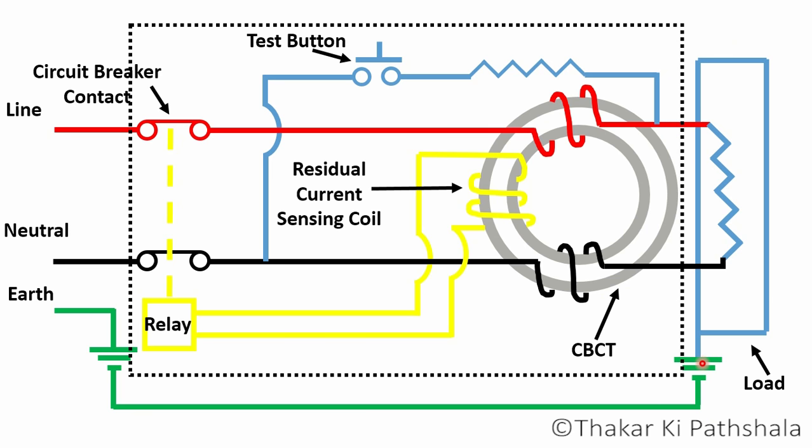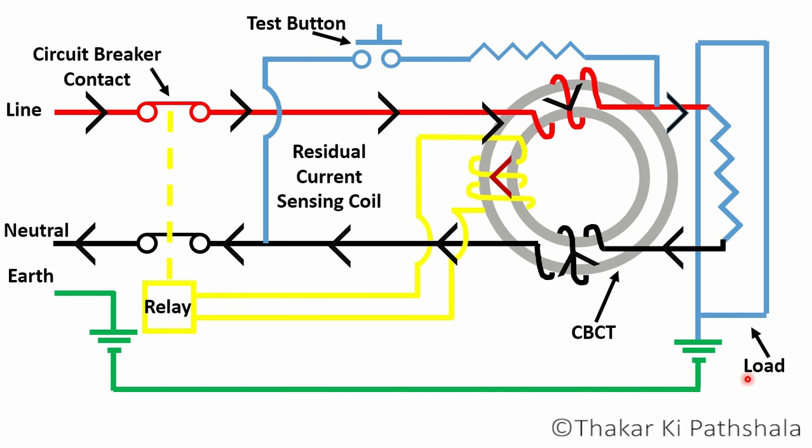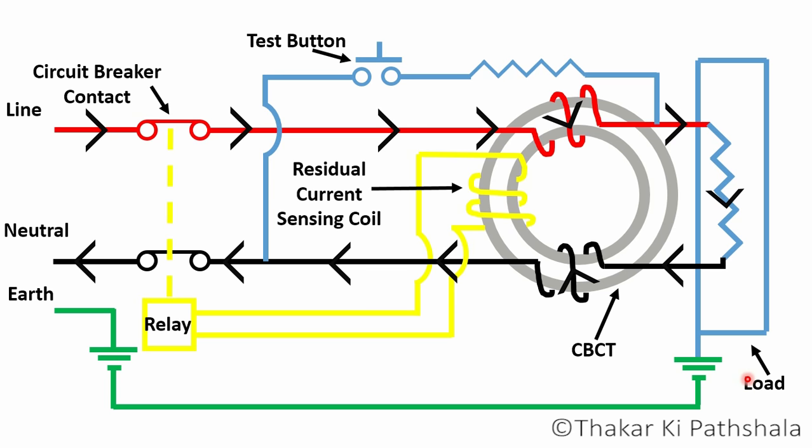Let's take the first scenario in which everything works fine. There is no fault. In this case, the current entering from the line conductor will be equal to the current leaving from the neutral conductor, but the direction of both will be opposite. So as per Fleming's law, the flux will induce in the core. But as the magnitude is the same and the direction is opposite, they will eliminate the effect of each other. So there will be no residual flux in the core of CBCT transformer. So no flux will link to the residual current sensing coil, and the system is working just fine.